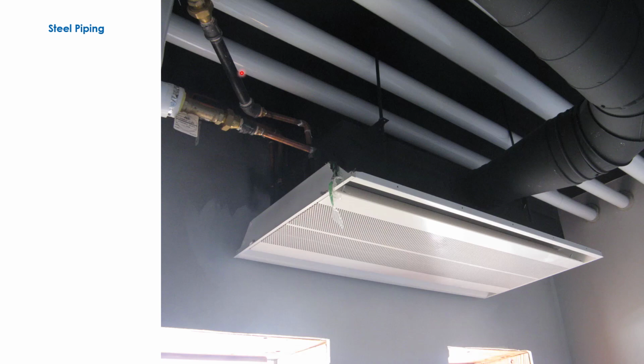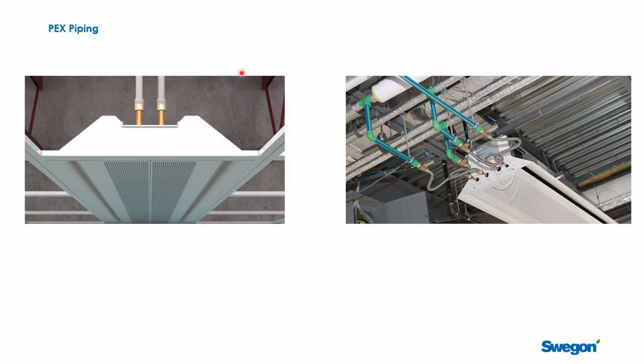It really depends on the engineer's preference for materials, and also what the best construction cost is for you in your territory in terms of what the contractor can run. And you hear a lot of talk about using PEX in chilled beams. It shows up in a lot of presentations, a lot of discussions in here. In the grand scheme, we don't see a lot of it being used yet. I think a lot of that has to do with local codes and acceptance in open plenums around fire codes and what have you. But as this material becomes more popular, this is a very cost-effective way to do it. It would really depend on your local codes and the engineer's comfort level with using this material. There's certainly no issue from the chill beam's point of view to use this kind of material.